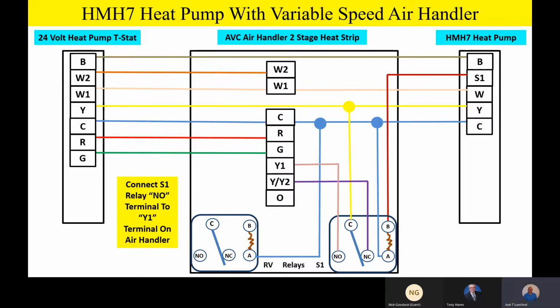Normally open contact on the S1 relay goes to Y1. That's our low-speed airflow. Now, where this is different on a variable speed air handler, the RV relay, all it's going to be doing is providing 24 volts to the O terminal, or the orange wire on this AVC air handler.